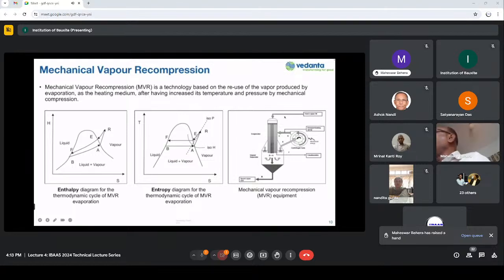From the top, the spent liquor comes and flows through tubes which are inserted in a shell. The shell uses fresh steam for the initial energy required to evaporate the solvent inside the spent liquor flowing through the tubes. When the mix of evaporated vapor and the concentrated liquor comes to the bottom of the chamber, the vapor is separated. This vapor is currently sent to the cooling towers for heat recovery. But after the implementation of MVR, the vapor is sent to the vapor recompressors.